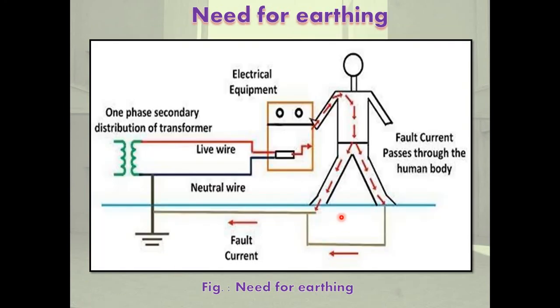Now, the third one is the need for earthing. The conductors in the plant are supported or insulated systems. The metallic structure and other non-current carrying parts are earthed via an earthing conductor connected to an underground earthing mesh. If earth leakage currents or fault currents flow via the earth structure and earthing mesh to the ground, the persons touching the faulted structure or standing on the plant floor are likely to get an electric shock, though not touching the conductor.